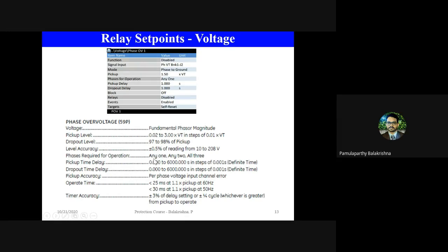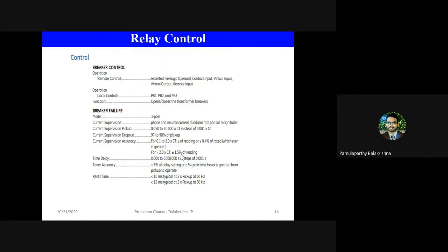That's a good question. What it is defining here is, if I mention this configuration as phase of operation as any one, it means that I have three phases, right? So if any one phase voltage crosses this level, I will take the action. If I select any two, only if two phase voltages cross, I will take the action. And if it is all three, only if all three phase voltages cross that level, I will take the action. So it is basically the flexibility of whether I need to operate for just a single phase overvoltage or I need to wait for at least two or three to also cross. Okay. Thank you. Thanks for asking.